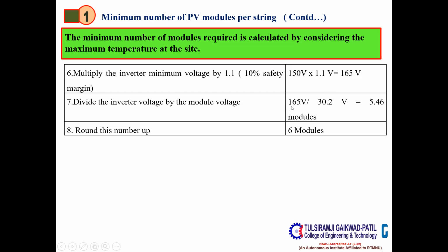So in order to get the number of modules, we would divide this 165 volt by the VOC output, which would be available with us if the cell temperature reaches the maximum. That is the cell temperature, not the site temperature. So 30.2, so we get 5.46. We would round up this 5.46, so we get 6 modules, based on the data specifications given to us for the PV module.